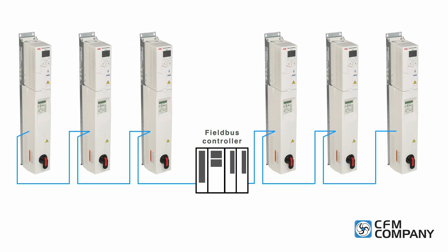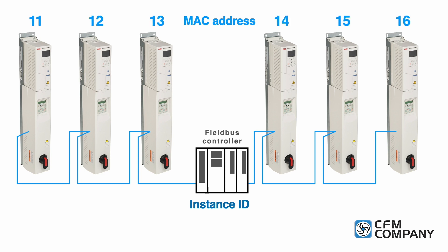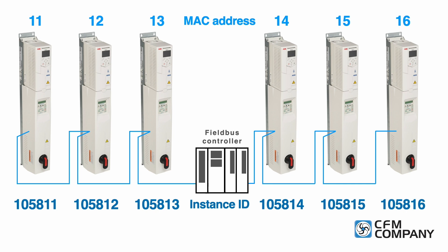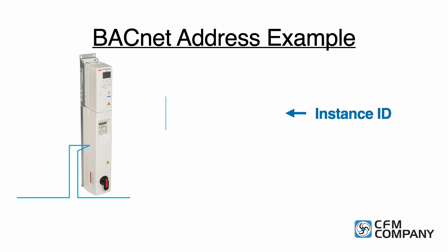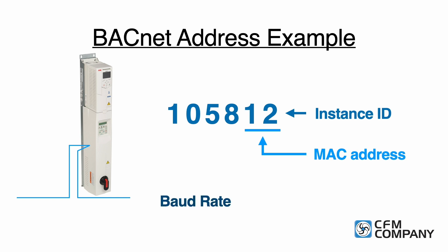Each device on the network needs to have a unique MAC address and instance ID. Ask the building automation contractor for a list of addresses for all the drives on the project. You will also need to know the network baud rate. For this video, we will use the instance ID of 105,812, where the last two digits of the instance ID is also the MAC address. The network baud rate will be 76.8 kilobits per second.